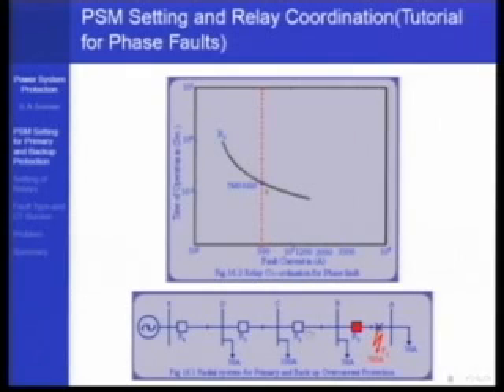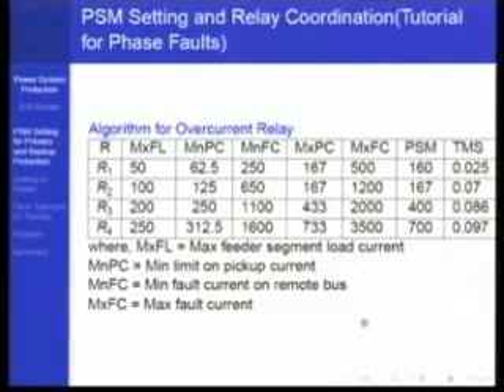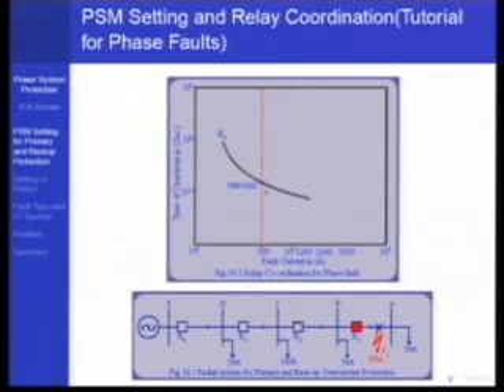Now to decide the TMS setting of R2, the fault can be anywhere on the section AB. I have to decide some value at which I will do the coordination. So I will look at the maximum fault current that the relay R1 can see, and that maximum fault current is 500. To coordinate R2 with R1, I choose the maximum fault current seen by R1, which is 500 amperes. At that point I find out the R1 operating time. To that I add 0.3 seconds, which is the coordination time interval, and that becomes the operating time for the relay R2.